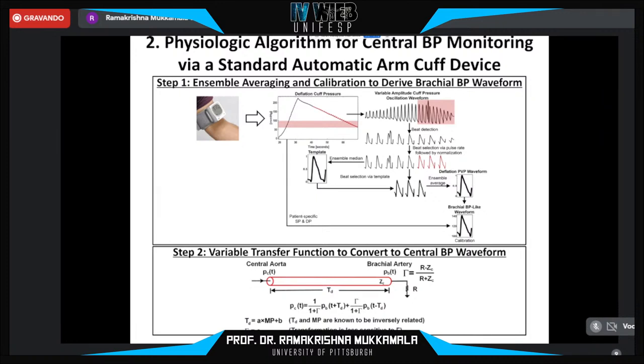First, the entire brachial blood pressure waveform is derived from the variable amplitude cuff pressure oscillation waveform measured by the device. This waveform is ensemble averaged over the lower cuff pressure range, wherein the arterial blood volume-pressure relationship may be more linear, after scaling the individual beats to equalize their amplitude and discarding atypical beats. The average single beat waveform is calibrated to the patient-specific systolic and diastolic pressure values to yield a brachial blood pressure-like waveform.